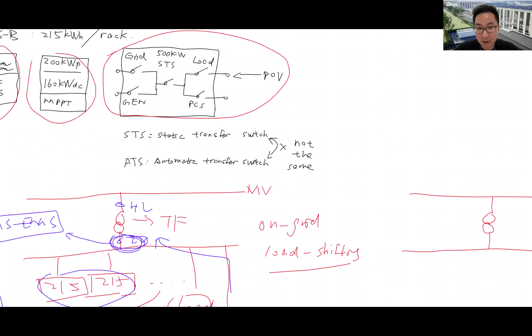What that means is, from the point of view of the load, whatever happens at the grid side, the load doesn't experience any fluctuation in power quality, because the moment the grid goes out, our 215, our PCS, will start supplying the load within 20 milliseconds of switching time. That's why it's STS. From the point of view of the load, everything is static, nothing has changed.